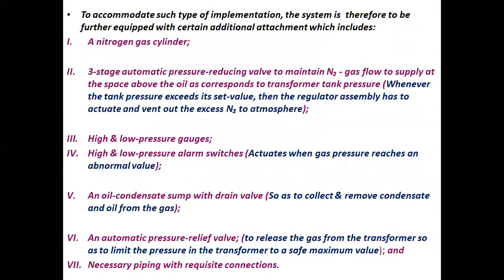To accommodate such an implementation, the system is further equipped with certain additional attachments, which include: 1. A nitrogen gas cylinder. 2. A 3-stage automatic pressure reducing valve to maintain nitrogen gas flow to supply the space above the oil, corresponding to the transformer tank pressure. Whenever tank pressure exceeds its set value, the regulator assembly has to actuate and vent out the excess nitrogen to the atmosphere.